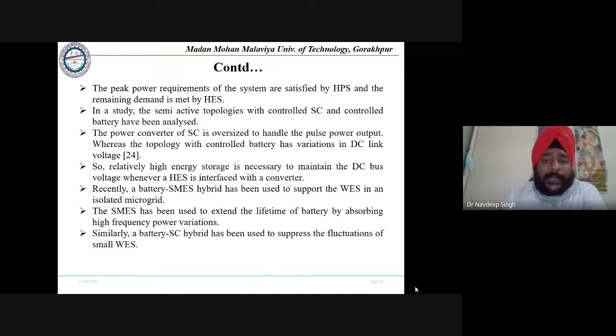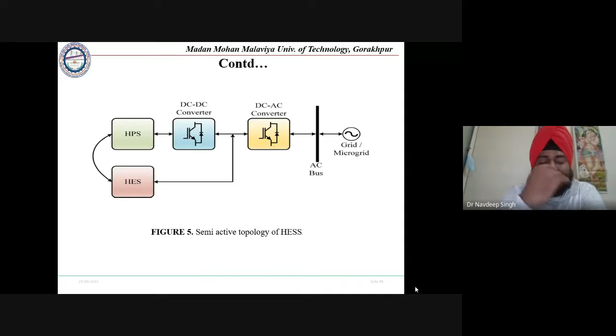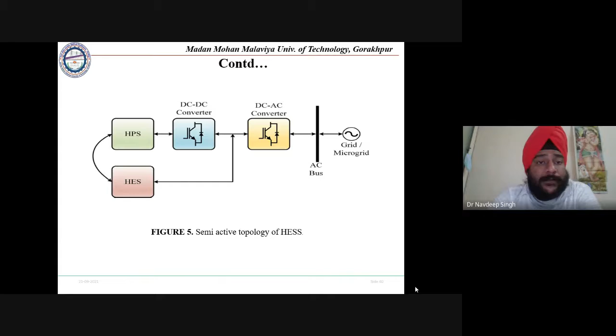So another option is to provide a supercapacitor. If we take a short time operation, where the time constant of the system is low, we will use the supercapacitor. If we have high power and a high time constant, meaning the inertia of the system is high, then another solution is a flywheel energy storage. For example, in a wind energy system, the inertia is very high, so this solution is used. In this case we are not providing a supercapacitor, and very fast active devices are not connected to the system, because it is directly connected to the DC common bus. So we will provide a flexible and reliable system, with a battery system and a flywheel system to maintain the inertia in the case of the wind energy system.